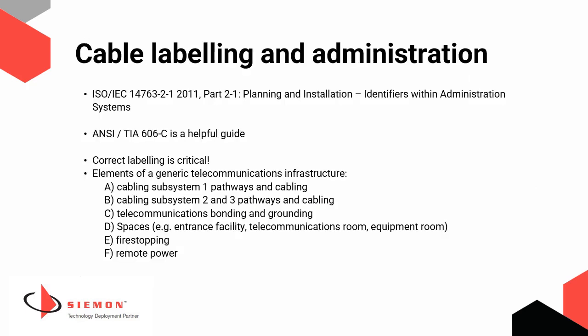Cable labeling and administration does form part of ISO 11801 under ISO IEC 14763-2-1. There is also a TIA standard that can be helpful, which is the TIA 606C. Correct labeling and record keeping is a critical part of any cabling system. As we show here, there is more than just cable that should be identified. Cabling subsystems, of course, but also their pathways. The bonding and grounding system, the spaces in the system like the telecommunications room or the entrance facility, fire stopping if it's been done, and also remote power.